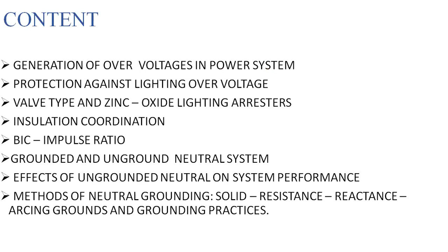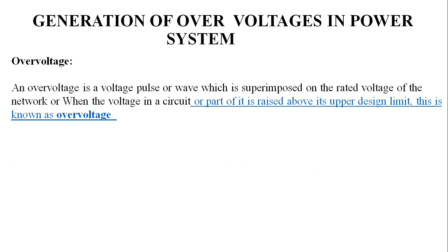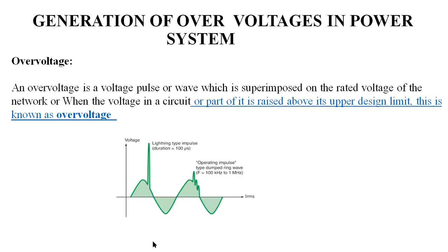What is meant by an overvoltage? An overvoltage is a voltage pulse or a wave which is superimposed on the rated voltage of the network, or when the voltage in a circuit or part of it is raised above its upper design limit. This is known as overvoltage. If you observe in this picture, these sudden spikes are a transient, a lightning type impulse. Its duration will be 100 microseconds. Its operating pulse is a damped ringing wave, with a frequency of 100 kilohertz to 1 megahertz.